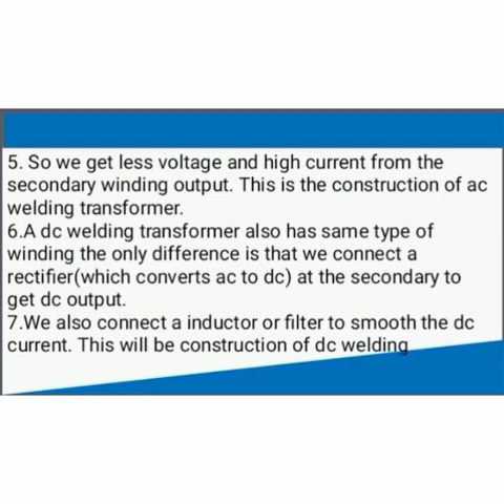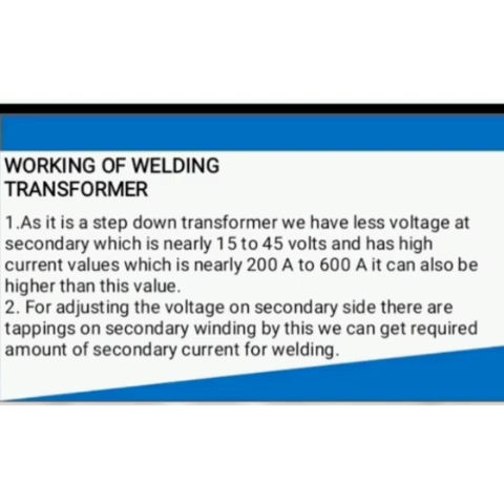Working of welding transformer. As it is a step-down transformer, we have less voltage at the secondary, which is nearly 15 to 45 volts, and high current values, nearly 200 ampere to 600 ampere. It can also be higher than this value. For adjusting the voltage on the secondary side, there are tappings on the secondary winding. By this we can get the required amount of secondary current for welding.